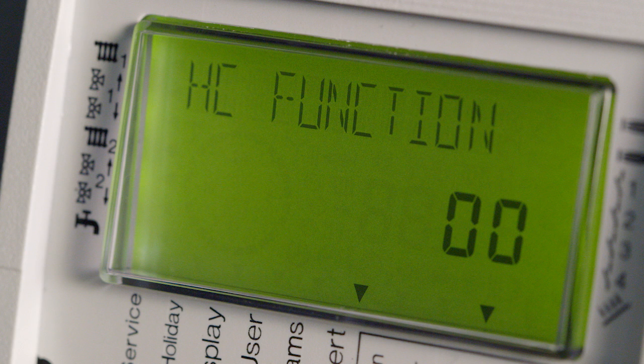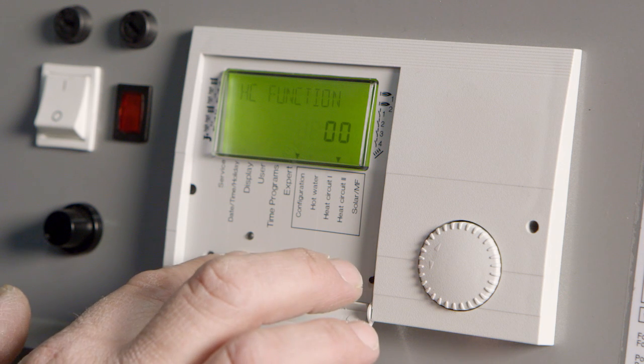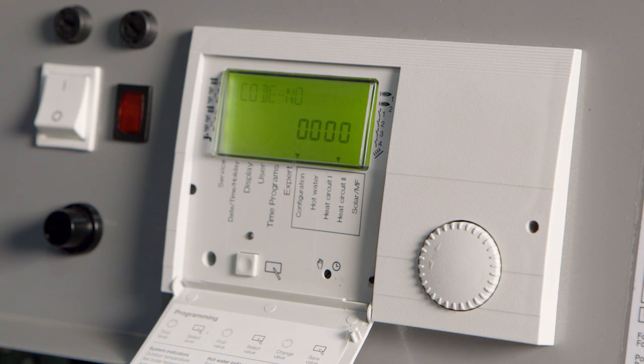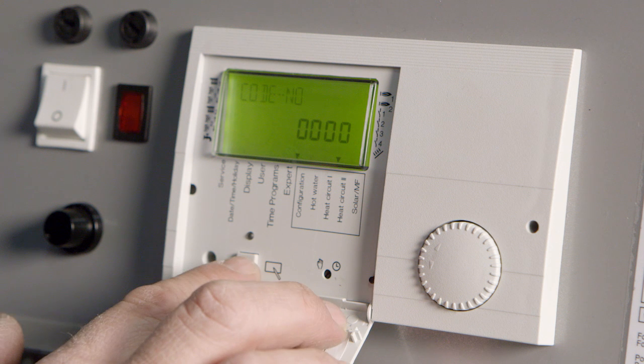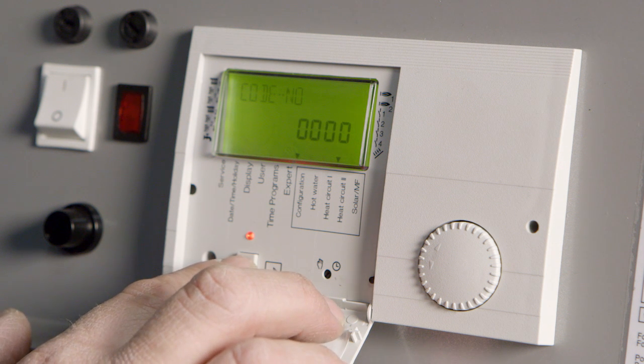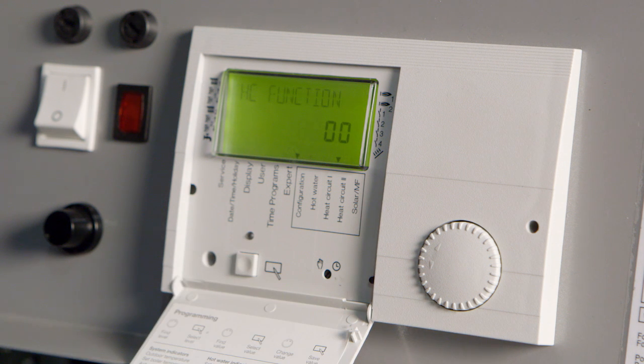Normally, 00 will show up, since this is the default value when the unit leaves the factory. For constant set point mode, the heating circuit function must be changed to 01. If you find that the setting is already at 01, disregard the next few steps in this presentation. Now, if the heating circuit function is set to 00, press the program key. Code number will appear. Enter 4 zeros by pressing the program key 4 times. Hit the button a 5th time to continue.